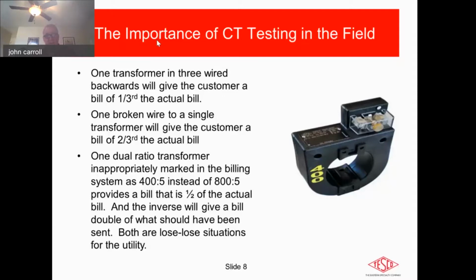We appreciate the safety aspect, and we appreciate that there's an energized circuit behind those. But if they're not tested in service, then you really don't know exactly what that meter is receiving. And as you can see, the other issue is on the nameplate. If there's an incorrect ratio stated on the nameplate, you can get significant changes in your bill. And that's not something anybody really wants.